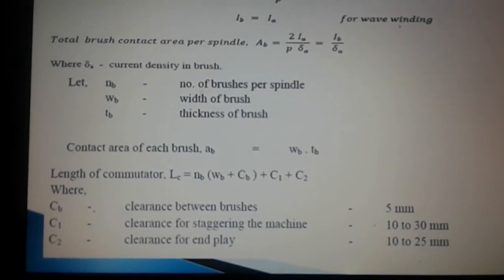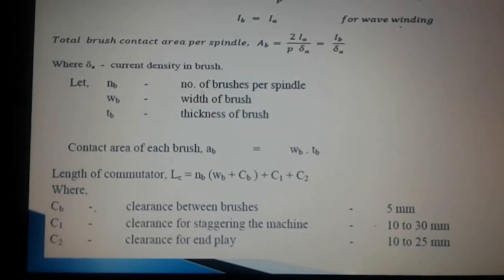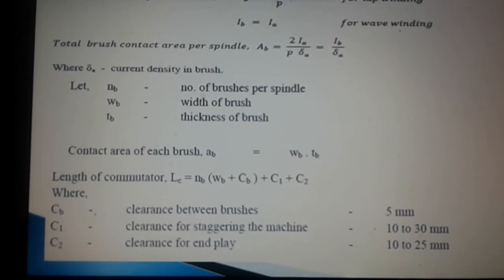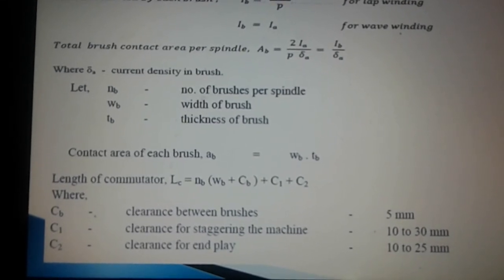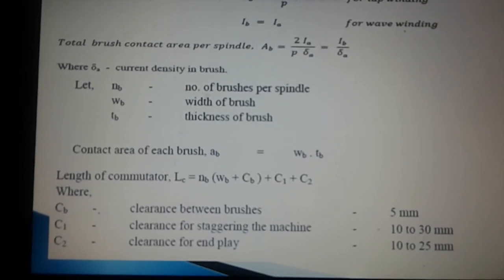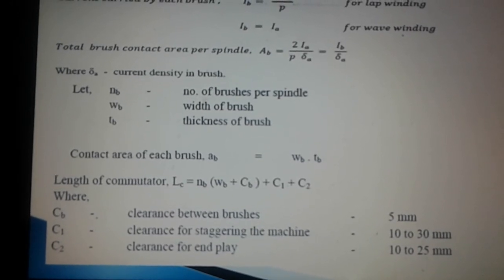C1 is the clearance for staggering and C2 is the clearance for end play. The values lie between 10 to 30 mm for staggering and 10 to 25 mm for end play clearance. The clearance between brushes is 5 mm.